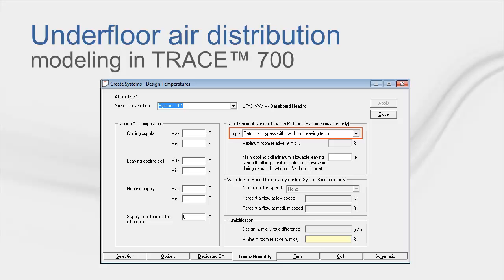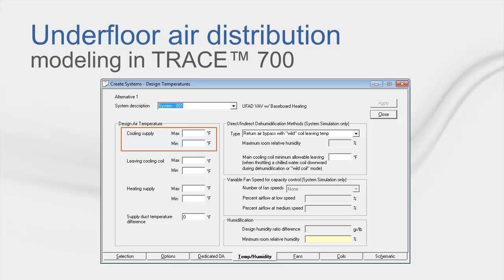By default, all UFAD systems will have a supply temperature of 63 degrees Fahrenheit. This can be changed by editing the temperatures in Create Systems' Temp Humidity tab. Trace defaults to 63 degrees F because it is sufficient to meet the thermal comfort at the feet of the occupants. Otherwise, too cold of air will be uncomfortable.